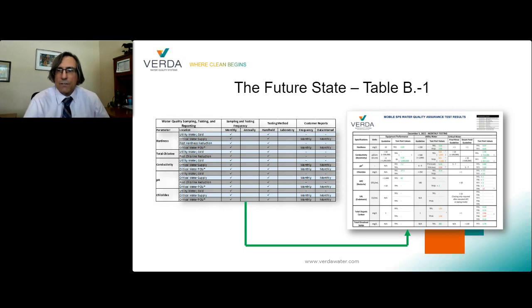In both of these cases, we go into the department, take samples, and then test them immediately with a handheld device. This is important for pH of critical water. The carbon dioxide and air react with critical water, and within a very short period of time will change the pH of the sample. If we send this to a lab that might not test it for days, the reading would be inaccurate. For other chemical analysis that can wait, and can't be tested on site, we will send those values to a laboratory. Then every month, the information is summarized in a report that is provided to the customer so they can demonstrate compliance.